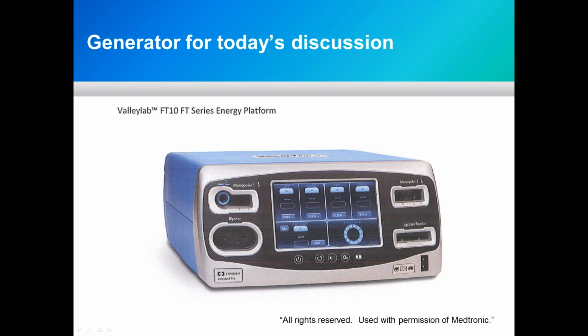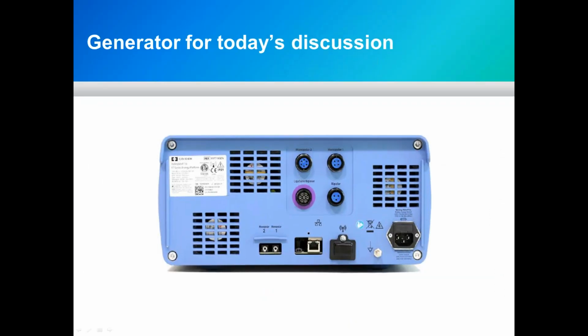There are two monopolar ports. Monopolar 2 is the port that would use the Valleylab blended tool, and there is just but one LigaSure tool for use with this unit. You also notice that there are no red lights scanning down on the instruments. All of the surgical instruments used with this device have RFID tags in them that monitor the usage of the device. So I mentioned it is much smaller. It is also much faster. It's about 100 times faster internal bandwidth than the Force Triad, and to a surgeon, that will make a difference as far as impact on tissues.